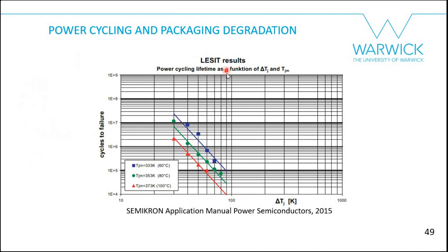The LESIT results show curves for mean temperatures of 60°C, 80°C, and 100°C evaluated at different ΔT values. Increasing mean temperature reduces the number of cycles to failure; increasing ΔT also reduces cycles to failure. Manufacturers provide these power cycling results for different ΔT values so you can apply them to your converter designs.